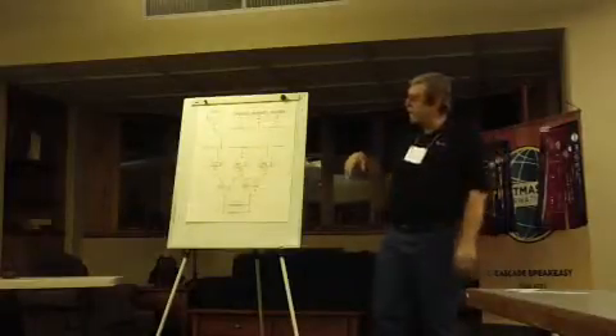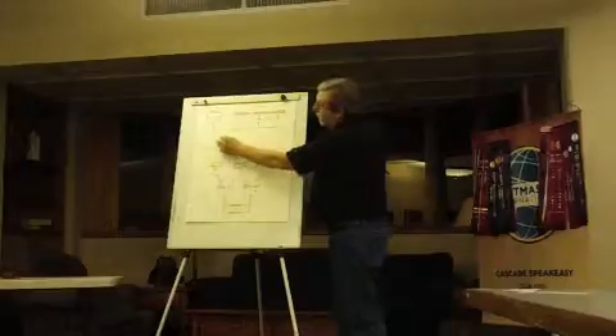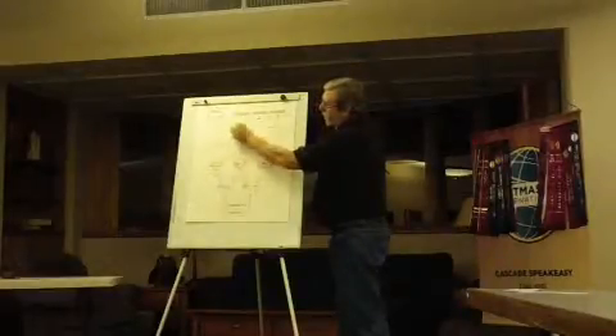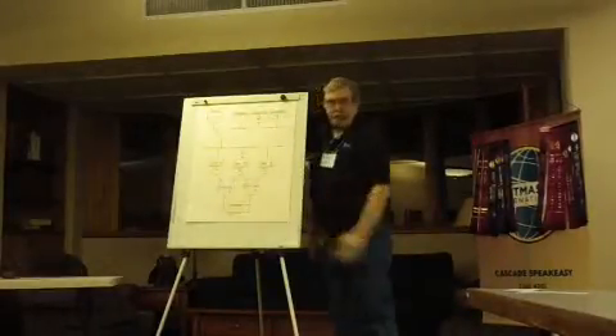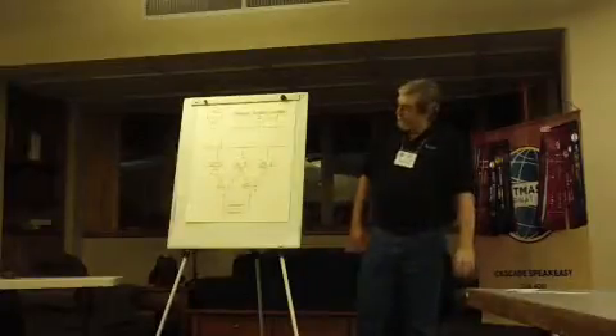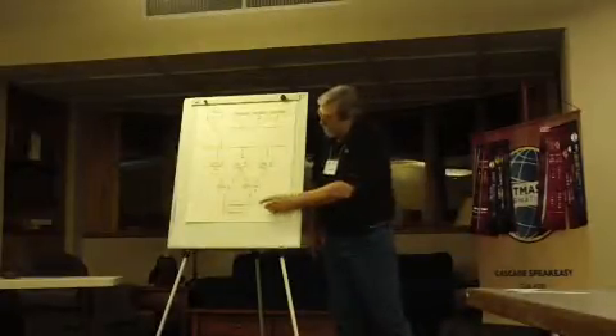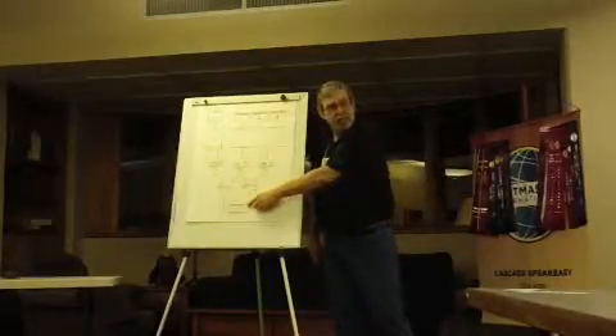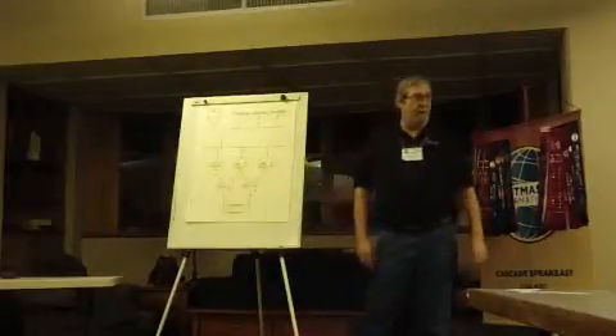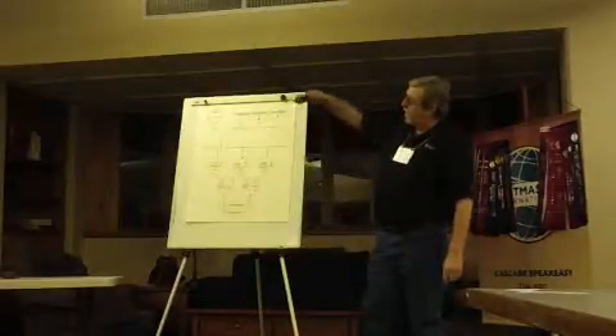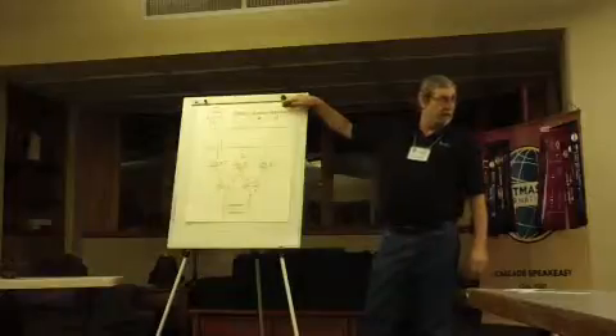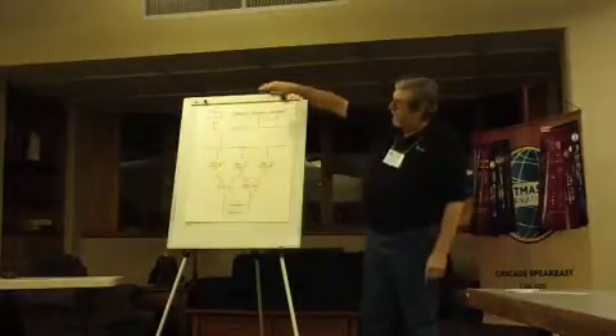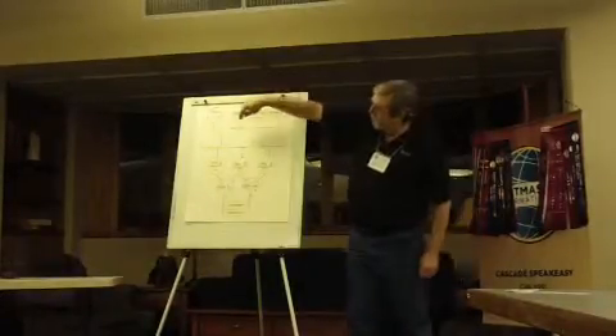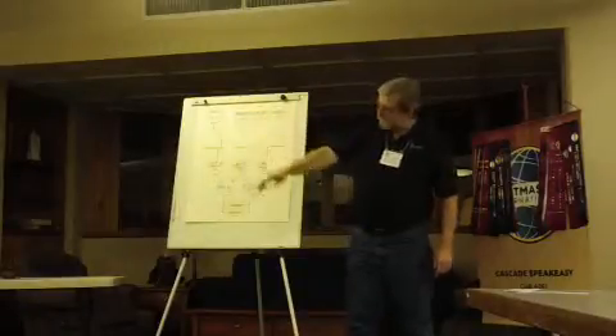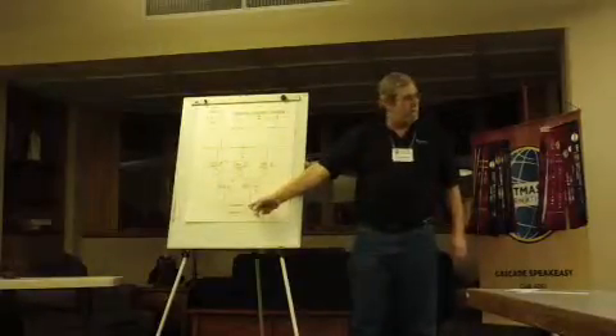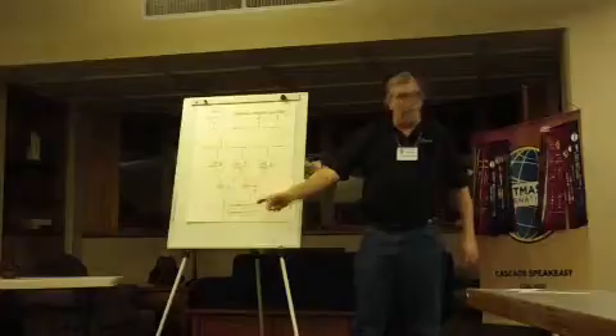And once they all sync together, now we're going to switch over here to their generators, and these generators are going to carry the rest of the building. Now, when I said earlier that it's unacceptable for these computers to ever turn off, that really creates a dilemma for us, because if the generators take 30 seconds to start, the utility is lost, there is no power coming down this way. So how do we keep these computer loads running while this is taking place?